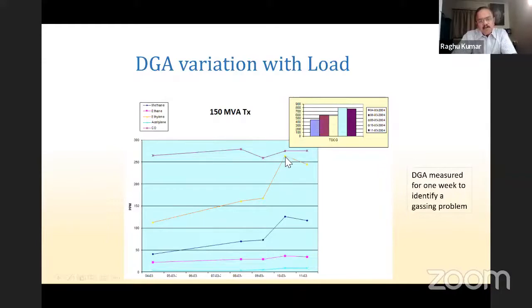See, if you look at this, this is the most important gas, which was above the warning limits. This is ethylene. And ethylene's presence is normally seen when there is a high temperature fault, like above 700-degree faults.